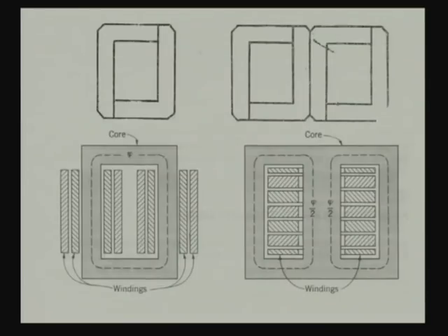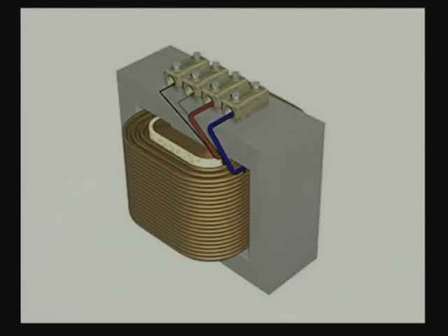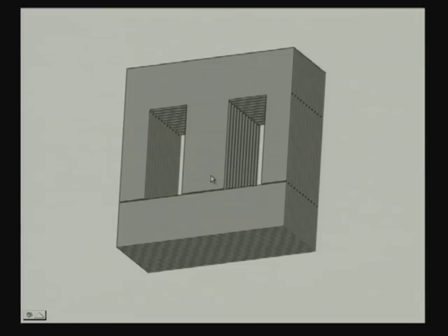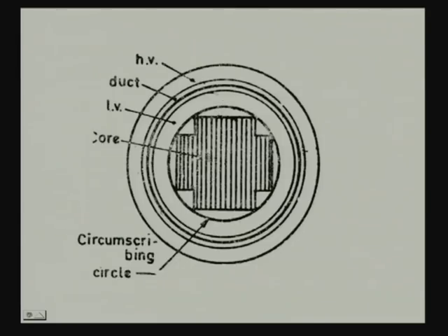If we look at the cross section of the central leg, then this is what we will find. The inside hatched portion shows the transformer laminations. On the lamination, usually a cylinder will be placed, which is made up of insulating material, so that it provides insulation between the core and the winding that will be placed next.